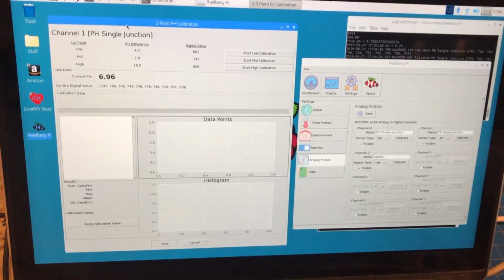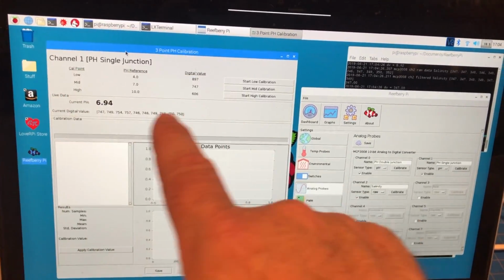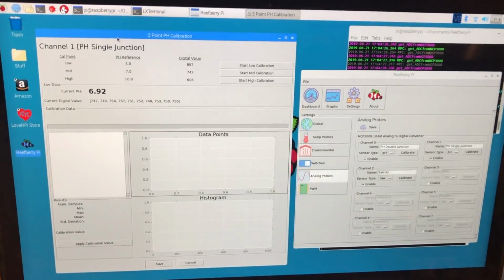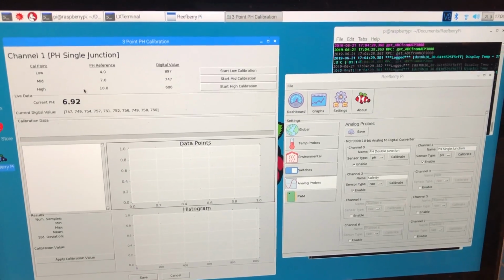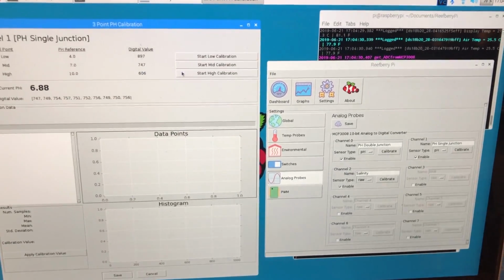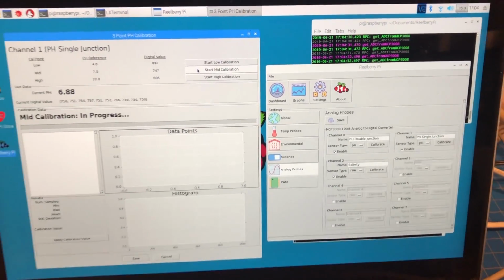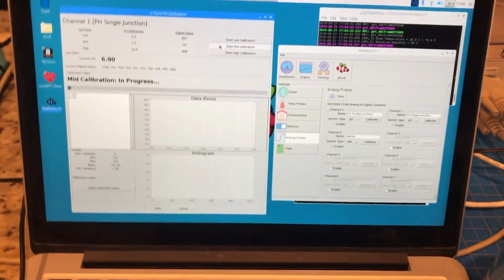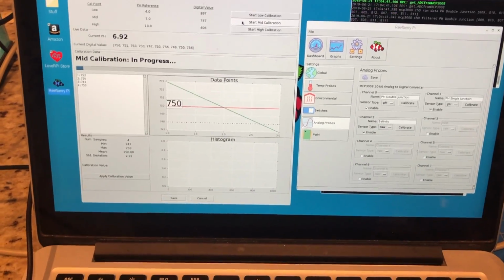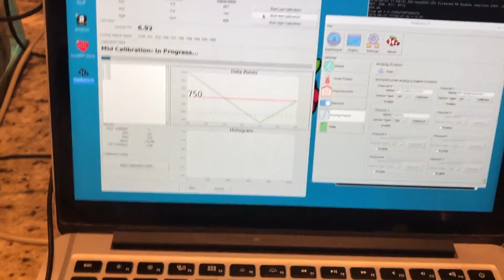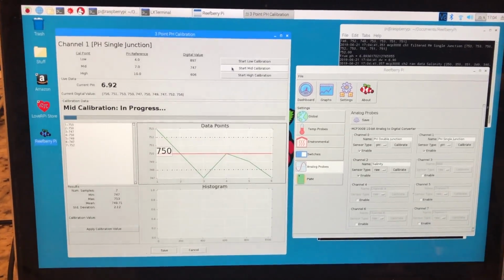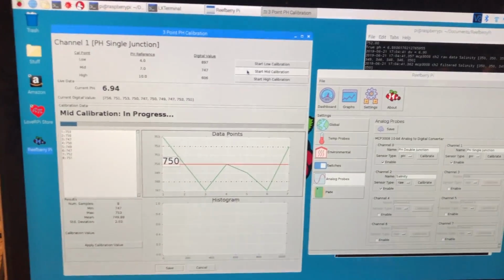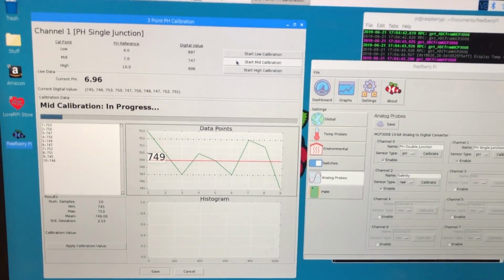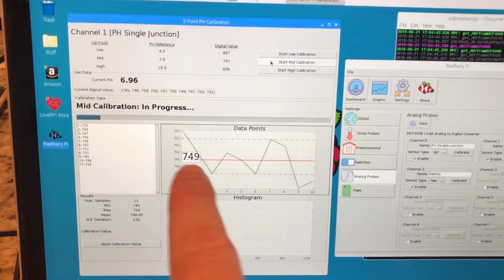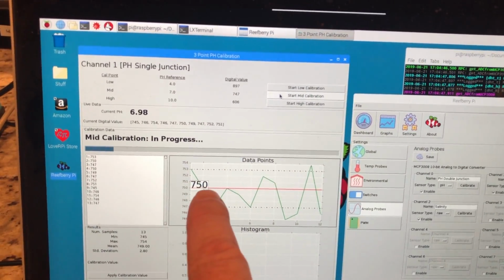So anyway, I've got that in the 7.0 reference solution, which is my mid, and we're reading 6.94, 6.92. That's pretty darn close. But let's say that we were going to be calibrating this anyway. I could click on Start Mid Calibration, and it's going to start acquiring data points. The way I have it set up right now, it will grab 120 data points just to calculate out where my target value should be.